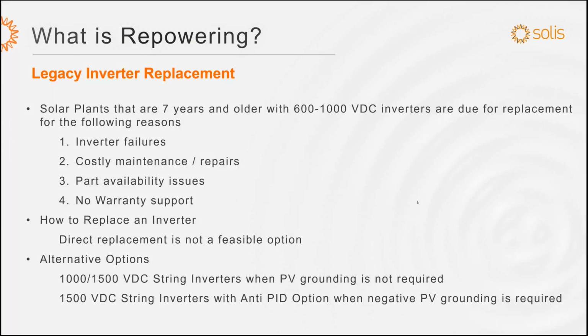So inverter failures are very common now with these 8 to 10 year old inverters. Costly maintenance and repair: even if it's possible to repair some of those inverters, it costs a lot of money to repair and service. Parts availability is an issue: a lot of the manufacturers that produced those inverters are no longer in business or no longer supporting those models. And then warranties: usually those inverters are out of warranty. They were 5 to 10 year warranties, and by now most of those warranties are expired.